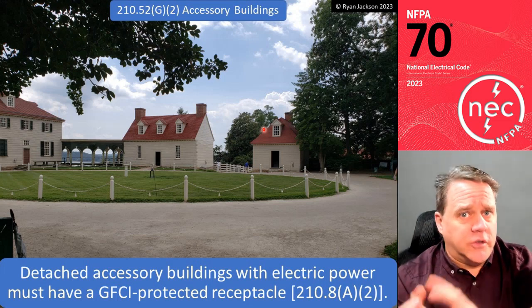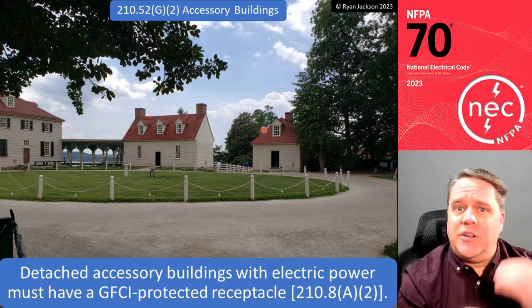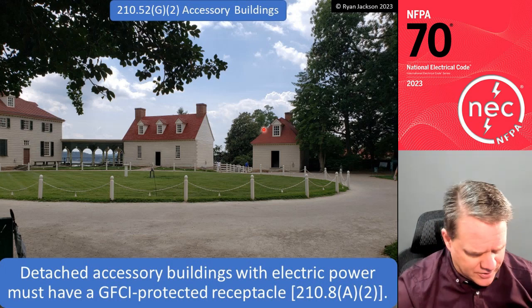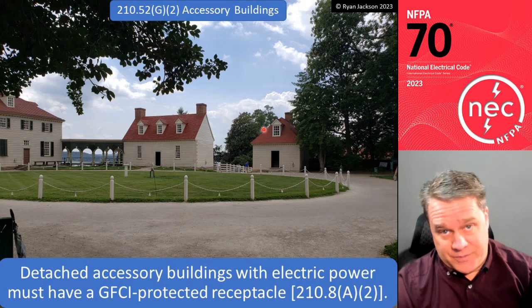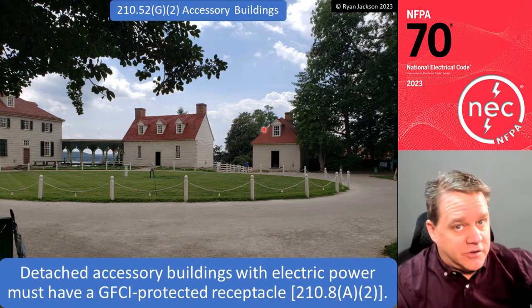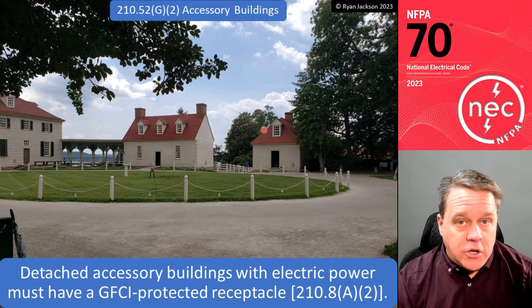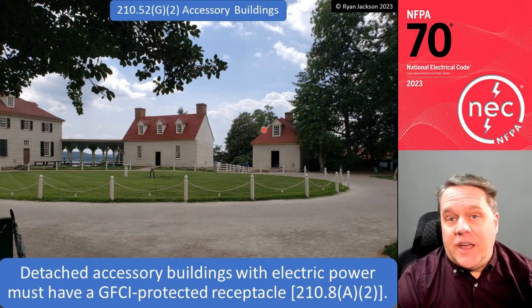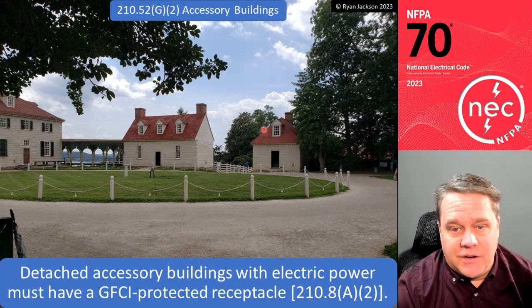And of course, those are only 2 prongs, so now they're biting the grounding terminal off the attachment plug and plugging it in and killing everybody. So, look, just put in a receptacle, all right? You don't have to run electricity to your detached garage, but if you do, you need to put in a receptacle. And 210.8 says it has to be GFCI protected.